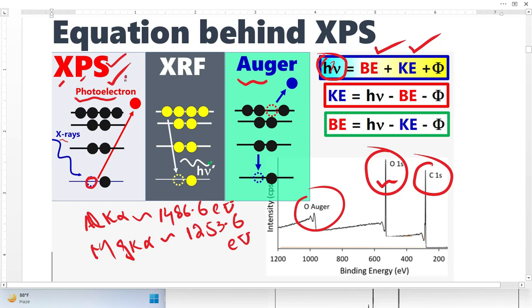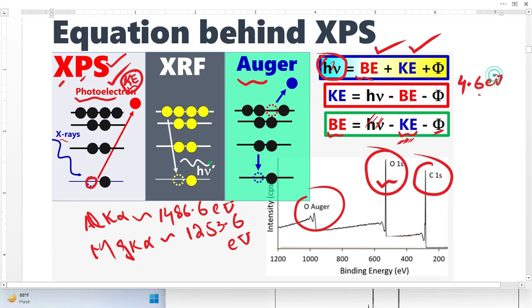We are only interested in knowing the kinetic energy of these photoelectrons. The XPS detector will analyze and detect this energy. When we rearrange the equation, we can easily calculate binding energy. We know the X-ray energy; the kinetic energy we get from the XPS spectrometer; and the work function for the spectrometer is a constant value — in most cases equivalent to 4.6 eV. So we can simply calculate the binding energy.